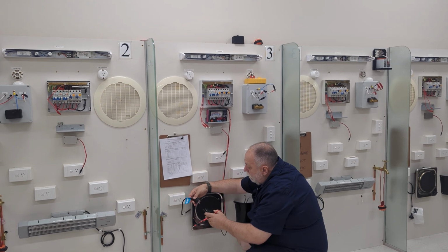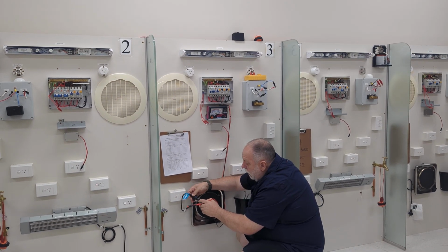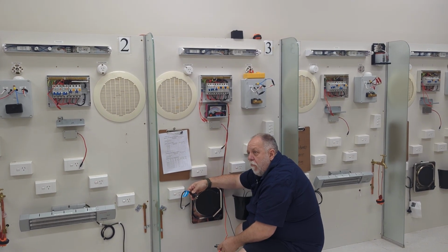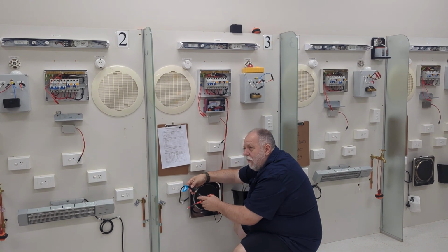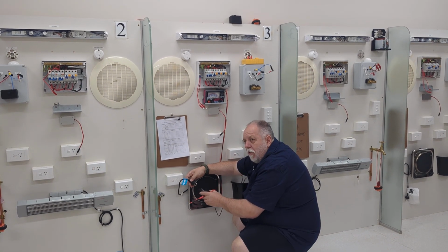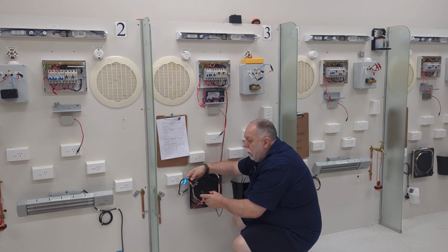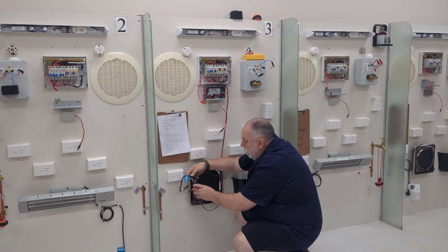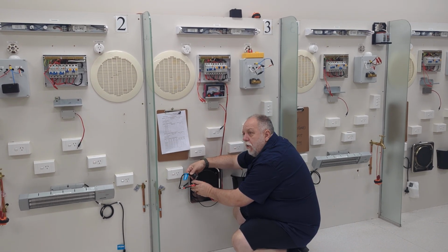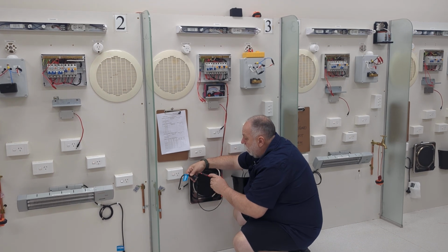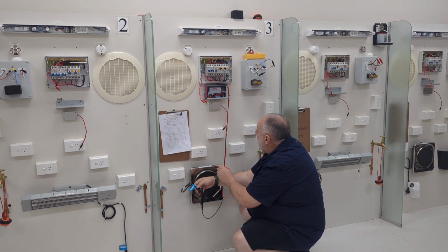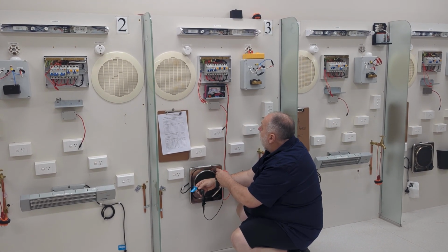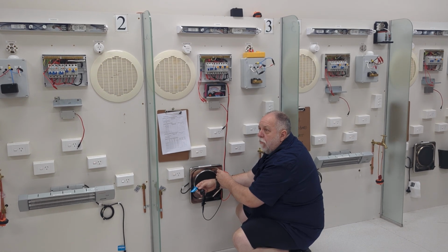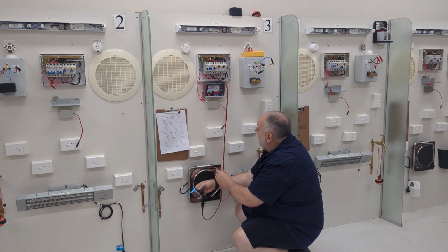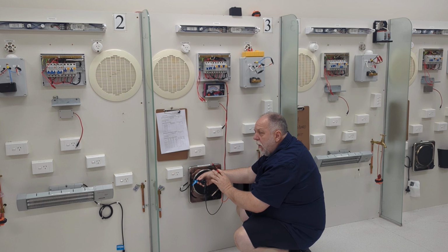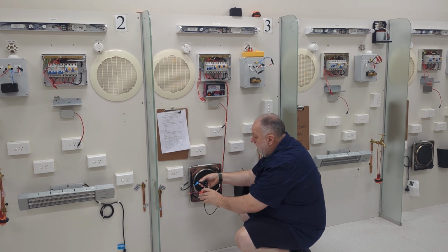one thing some kids got caught on yesterday as well. See how the earth pin here's got half plastic on it? Make sure when you're testing to the metal part, not onto the plastic. He said, oh, the earth's not doing this or doing that. I came in and we redid it, and he didn't realise he had the clamp sitting across on the plastic. Do you understand what I'm getting at? So I've done that. I'm going to now go to here. Beautiful. I've got 0.5 of an ohm, probably a value that I don't want to see, it's probably a bit too high, but at the same time it's still got an earth point to that door there.